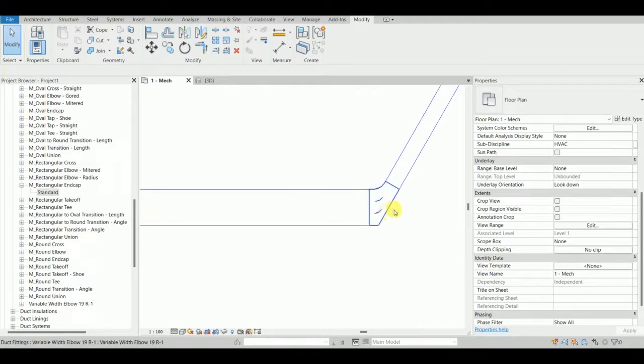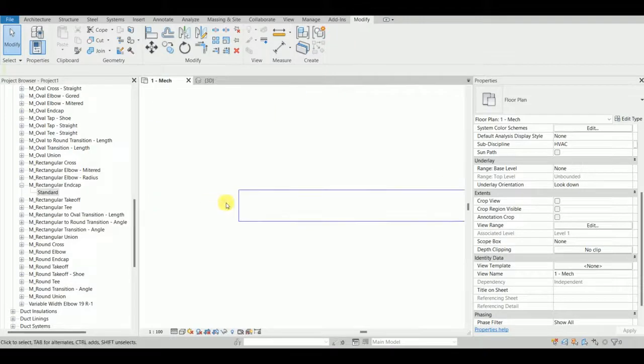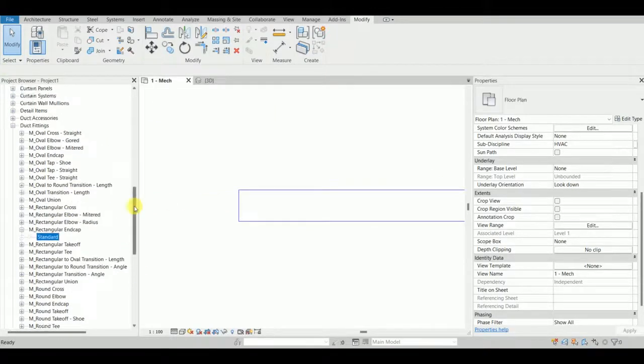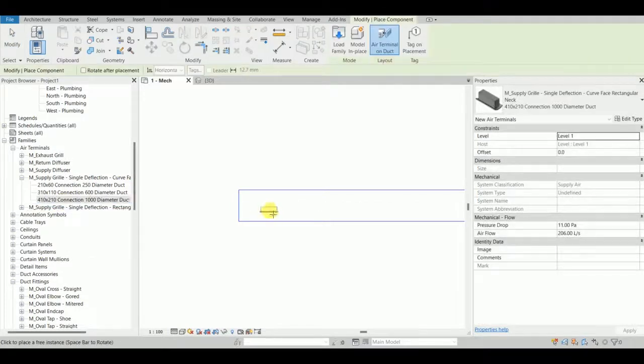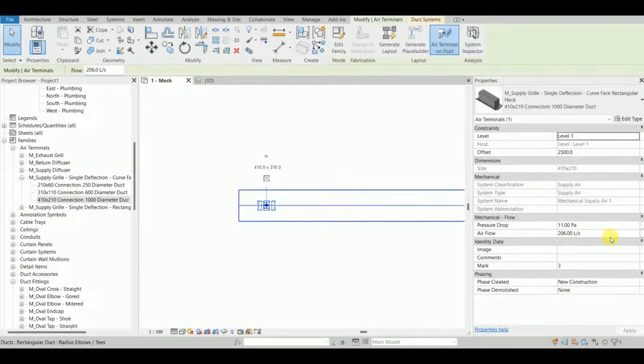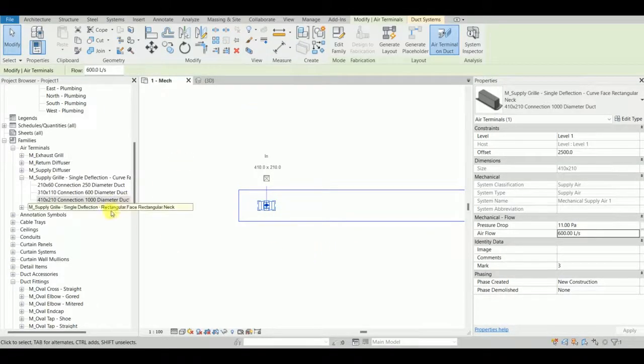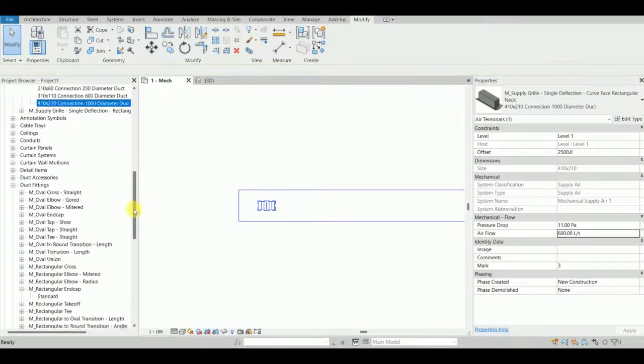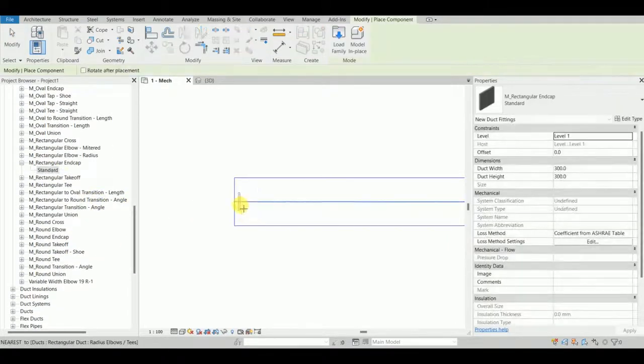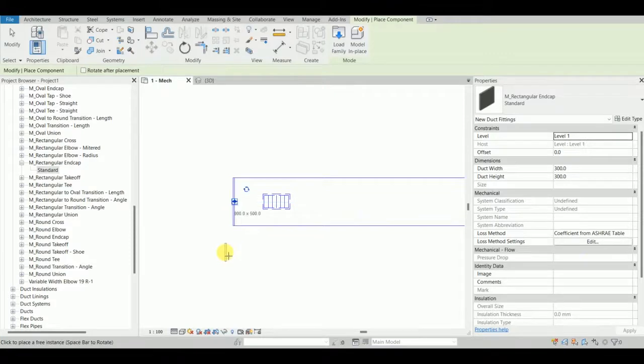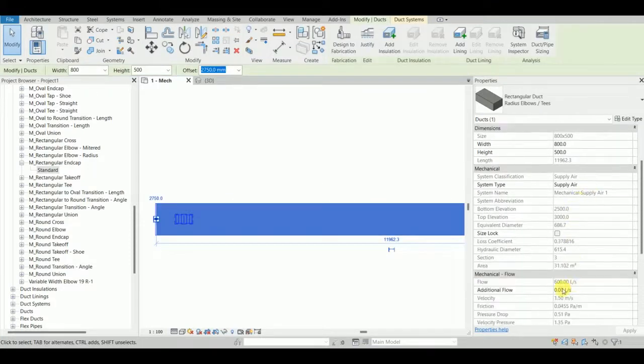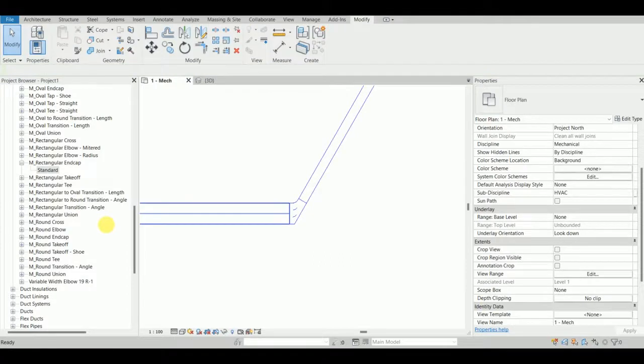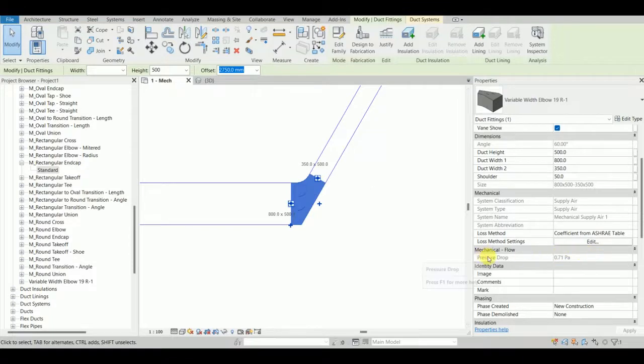Now let's see if it can do calculations for the bend which is not in the ASHRAE. I'll put the same example - a terminal on duct. This time let's say I put 600 liters per second. I bring the end cap and close this end. I've got 600, and yes, it is doing the pressure drop calculation.